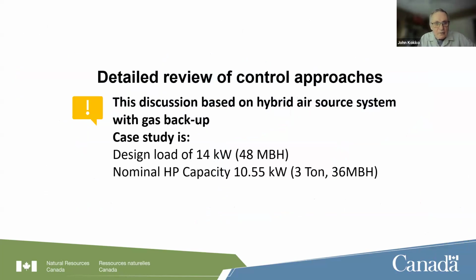So we are going to be discussing a hybrid air source system with gas backup, as I said. And when we get to the case study, it's looking at a house with a 14 kilowatt load, but the heat pump nominally has a 10.5 kilowatt output. And so we can almost immediately see that we're not going to meet the whole load of the house.